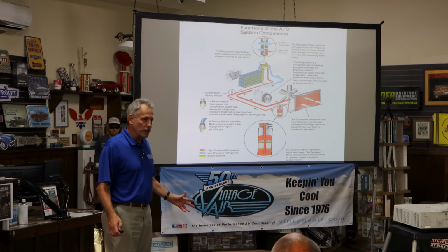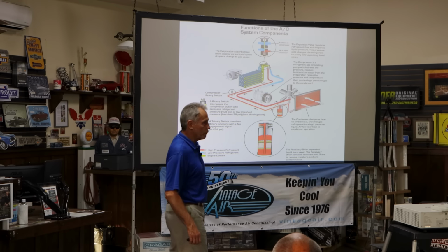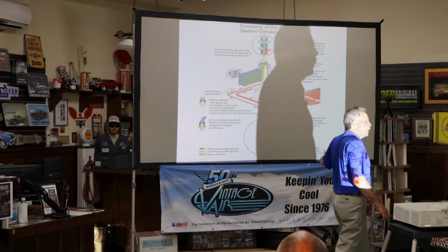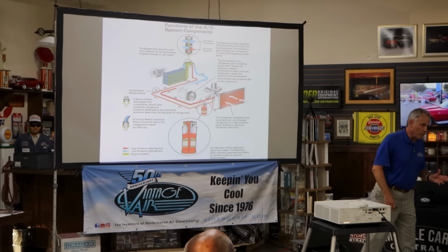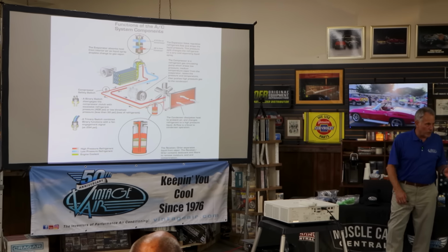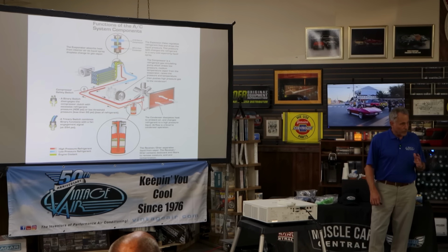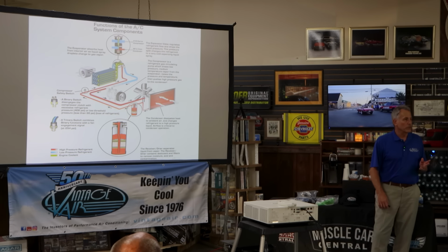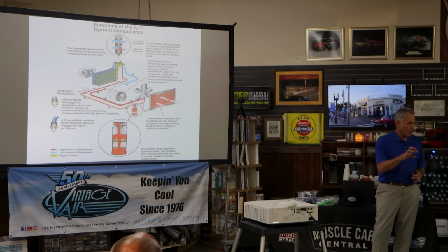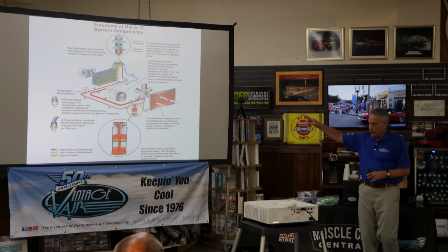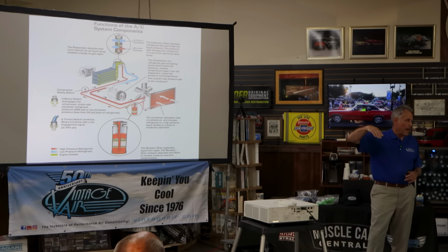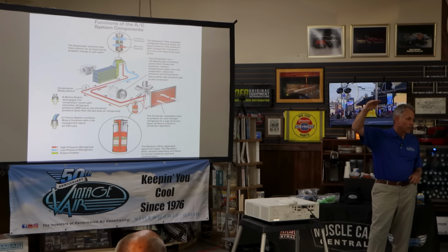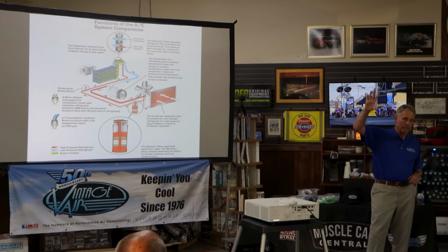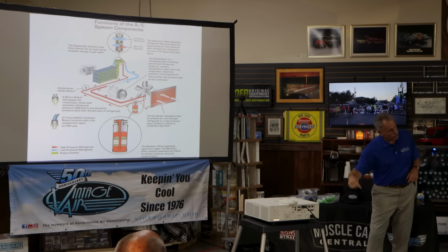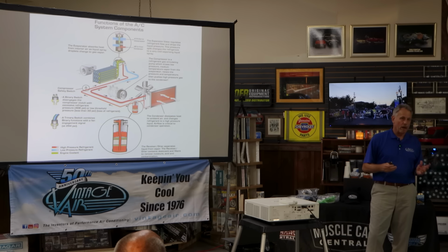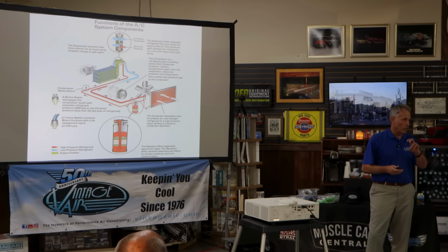That's an external freeze up, the system is frozen up, you can't blow air through it, so you're not removing heat from the air anymore. So at that point, the only thing you can do to run your system again is turn it off, let the coil temperature get back above 32. That ice turns to liquid, melts, goes to the bottom, and goes out through the drains. Now I can turn my system on and start over again.